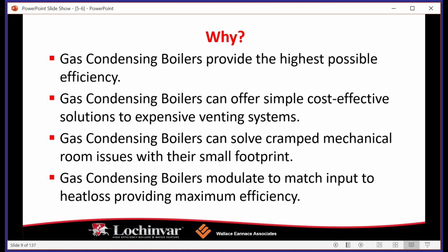So efficiency, when we discuss efficiency, efficiency is measured in our industry by something called the AFUE, or annual fuel utilization efficiency. You're going to see that represented by a percentage. Okay, so you'll see a lot of numbers get thrown around. Oh, we got 85%, we have 90%, we have 99%. Easiest way to really break that down and make it easy to digest is, say if you spend $1 on fuel. Okay, if you're running an older cast iron heat exchanger atmospheric vent boiler, it may be running at 80% efficiency. So what that means is, out of that dollar, you can say that 80 cents of your dollar got turned into energy in the form of hot water, and 20 cents of that dollar got wasted as latent flue gases just blowing out into the atmosphere.